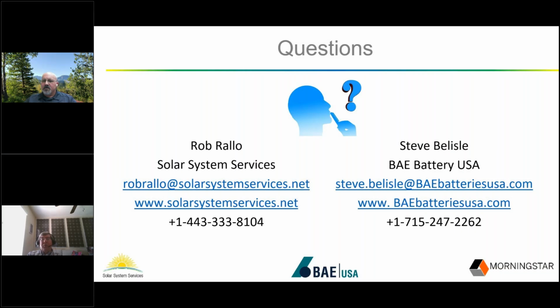I'd go back to IEEE 1562 again, which recommends 7 days or longer autonomy for critical loads. But the best way to really know for certain is to run a loss of load probability analysis, like I did in those graphs. That's really the only way to know for sure, because it depends on the size of the solar array, your location, the solar resource, and a lot of other factors. That makes it hard to just have a single chart or graph. It's easier to run a probability analysis and get your exact answer.